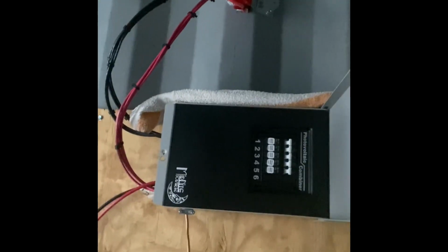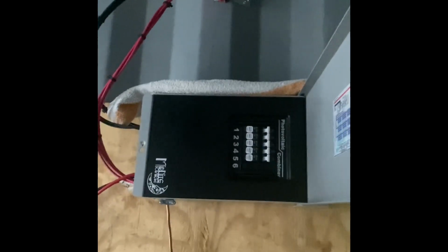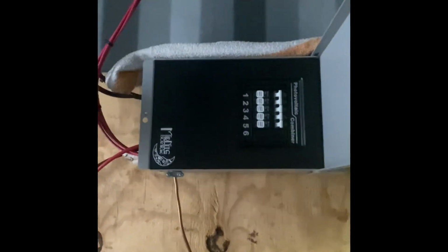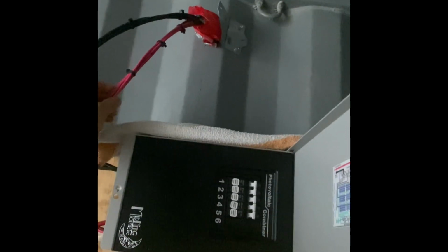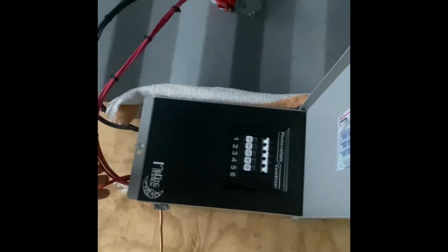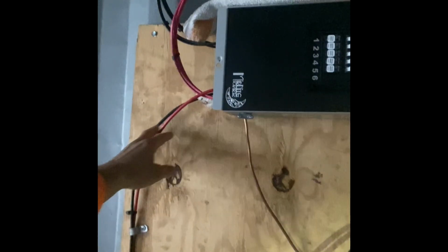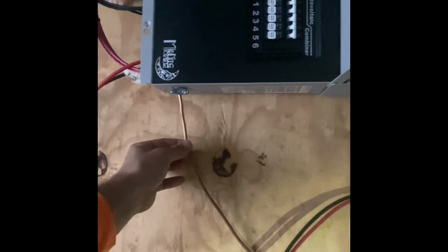If you're going to give 20 amps or 30 amps, if you plan for 30 amps, go with a wire that can handle 40 to 50 amps, just to be on the safe side. Otherwise, if you have an event where you're soaking these lines with higher amps than they can handle, these will catch on fire. There's no point of having a circuit breaker if the wire that's bringing the charge is overheating. I think the 10 gauge handles about 30 amps, 6 gauge about 55 amps coming out, something like that. 4 gauge ground rod.